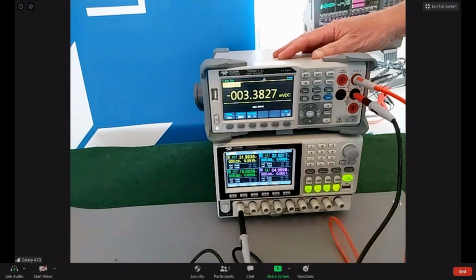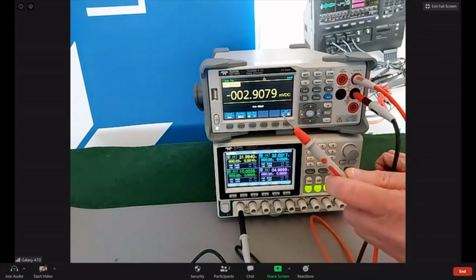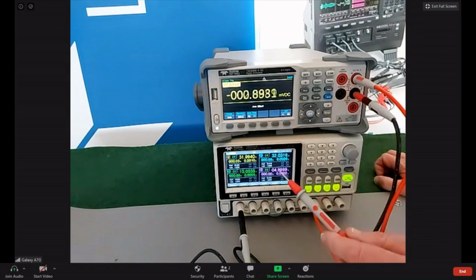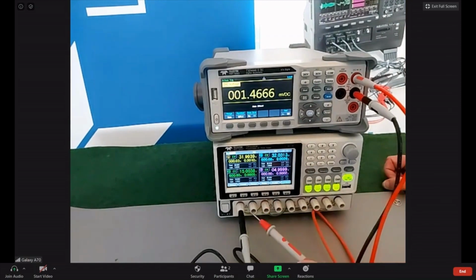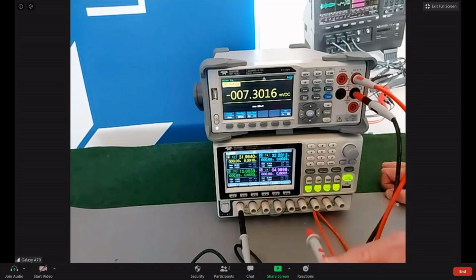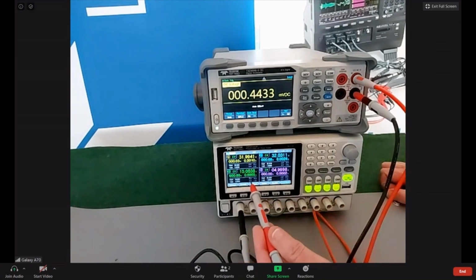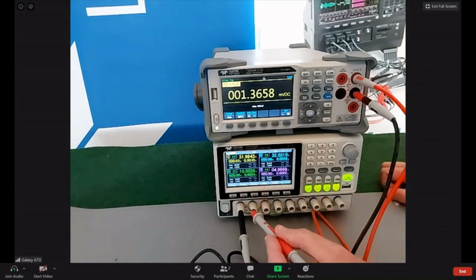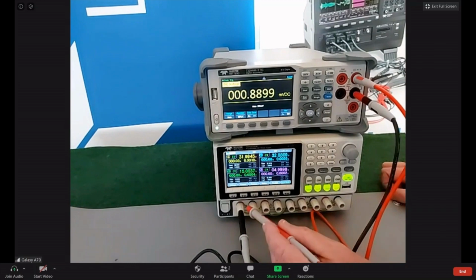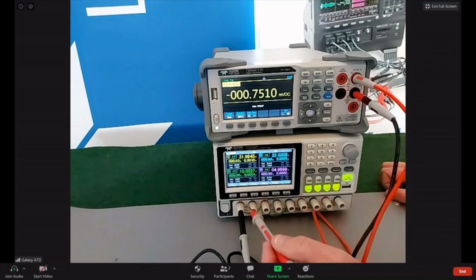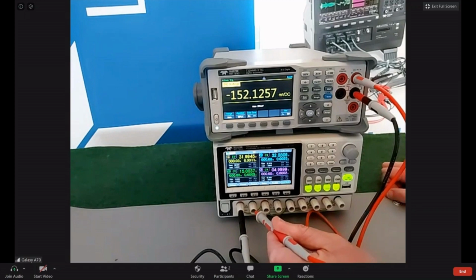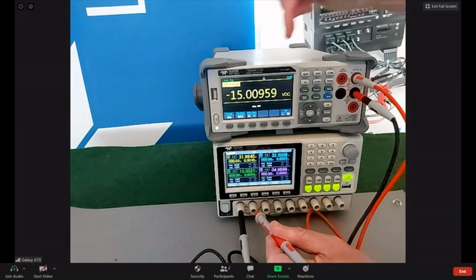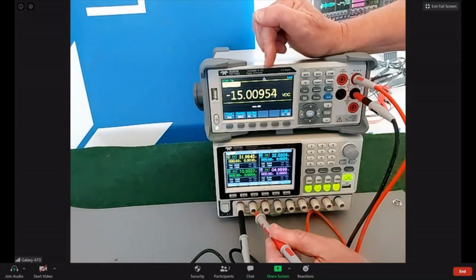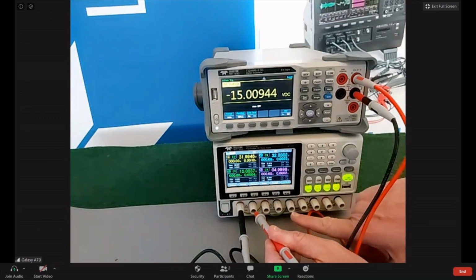So we've got our common line, and then we've got our measurement. Now we're going to measure each set. The first one is channel 4, set to 15 volts. Is that positive or negative? Well, because I've wired the positive onto the common line, this should be negative. So we put it on here, look at the DMM, and sure enough, we've got negative 15 volts.